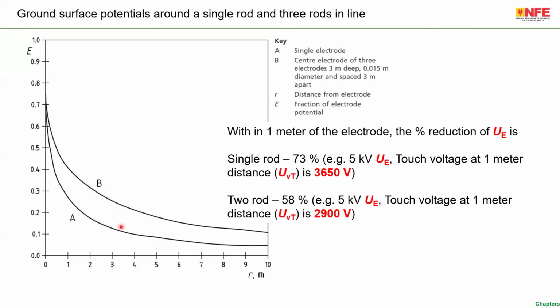From this particular graph, you can find this graph in the standard. If we apply 1 second disconnection time, in case of a single rod, 73% of the EPR gets reduced at a distance of 1 meter. That means if your UE, EPR or GPR is 5 kV, the touch voltage at 1 meter distance is reduced by almost 73%. That means from the exposed conductive part of the transformer to the place where you are standing 1 meter away, the potential difference is something about 3650 volt. Please note that this is applicable for an EPR of 5 kV. If you use 2 earth rods, then this voltage is a little bit less. Is this the solution? Absolutely no.